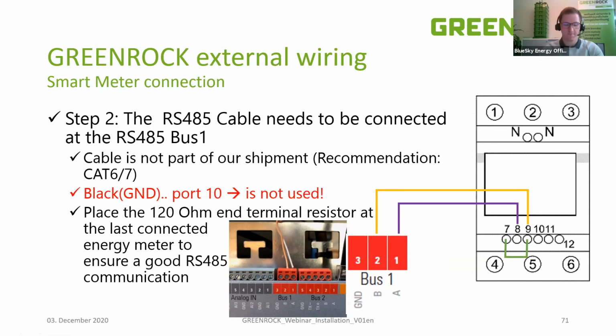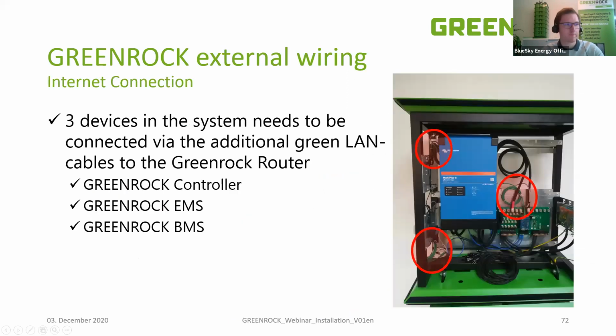And please also place, it's really just a wire, just an easy, small wire, which you need to make from pin 7 to pin 9. So this is more or less just a jumper. If this jumper is realized, inside the energy meter a 120 ohm resistor is active, which is the end terminal for the RS485 connection. So you don't need a resistor with you. You only need a short, small wire. Maybe just use one of the network cables, which you maybe have.